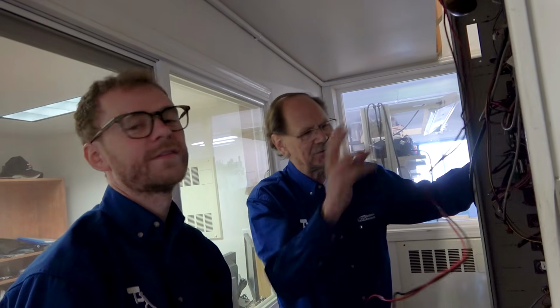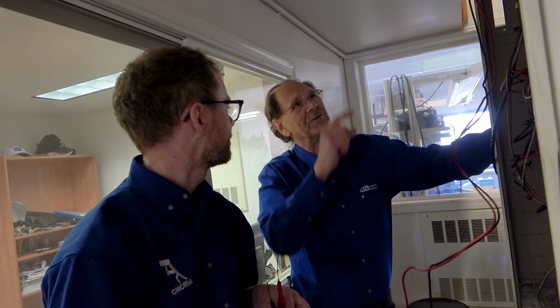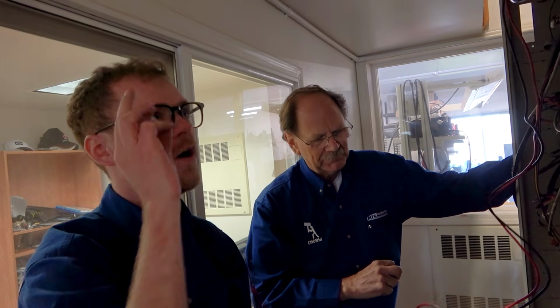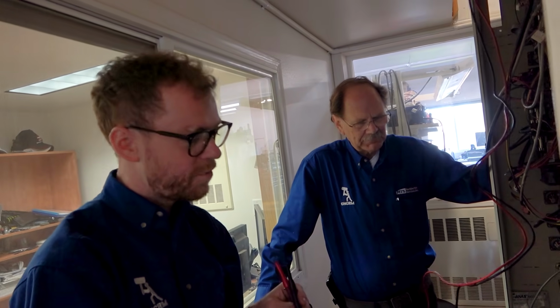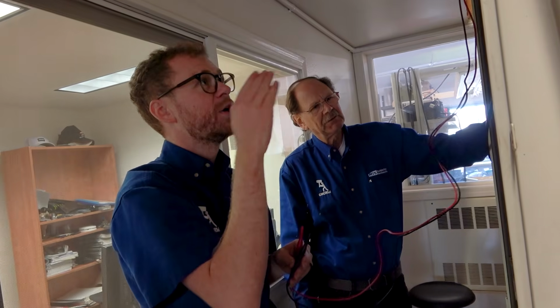There's nothing in this control cabinet that goes from one of those legs to ground. Everything is on the 3-phase and then through the transformer. After the transformer, that gets more electrically complicated. We'll make videos about that. But you shouldn't be measuring to ground when checking voltage. It doesn't matter. The machine just needs straight 3-phase. So check the other side.